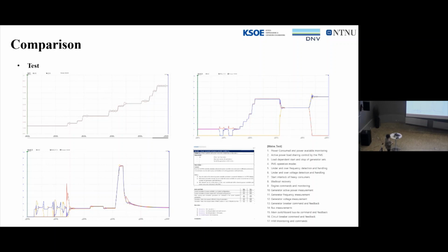And here the third generator is running and connecting to the same switchboard. Then the 2 generators reduce their load for load sharing. So 3 generators are on load sharing symmetrically here.